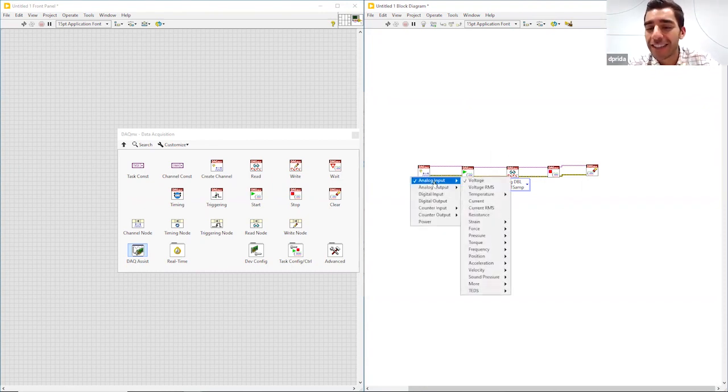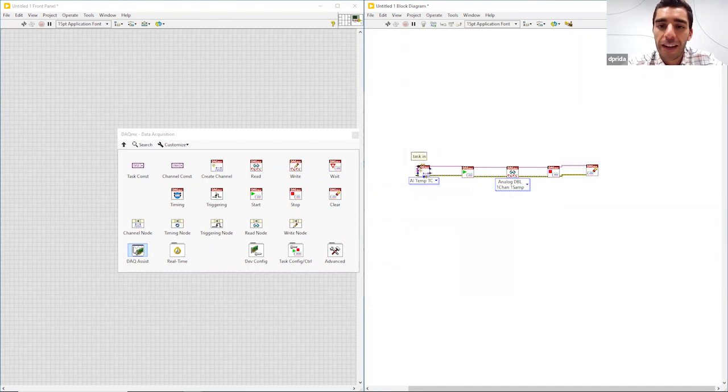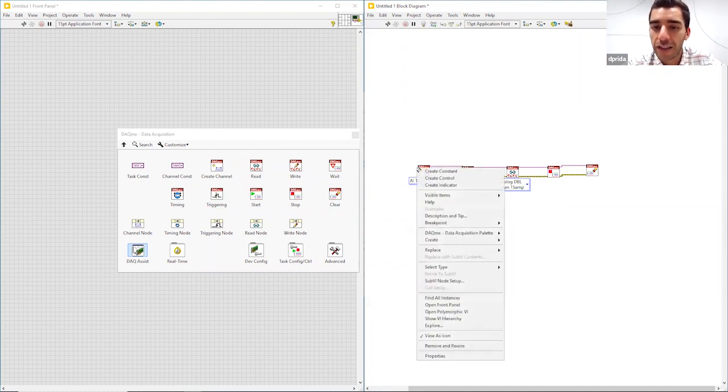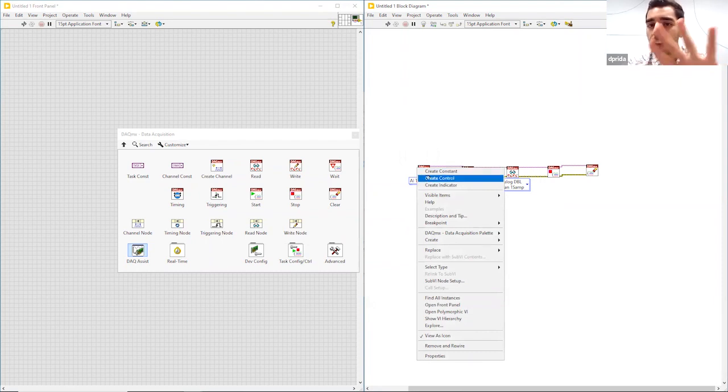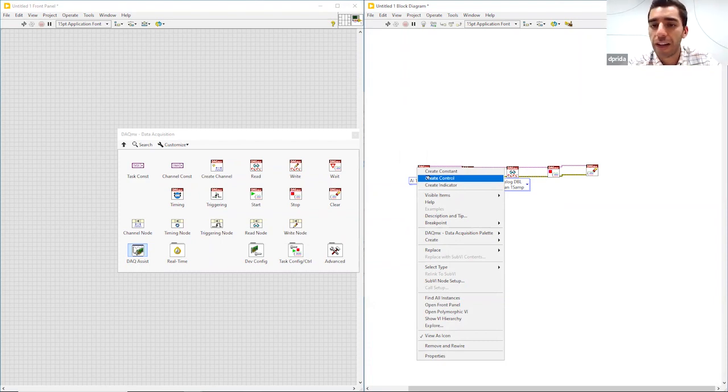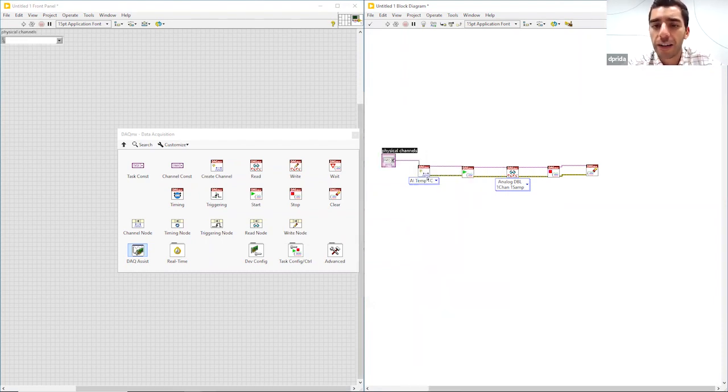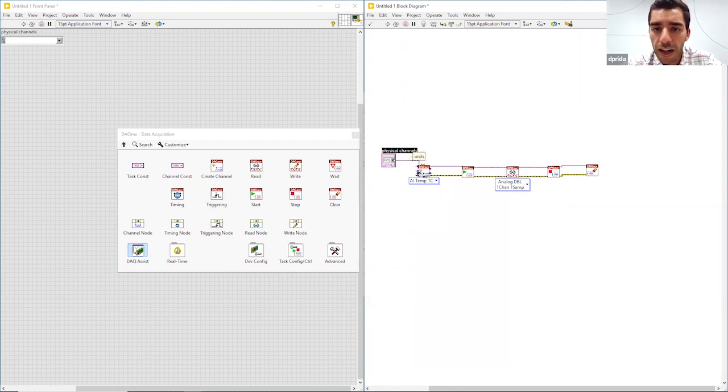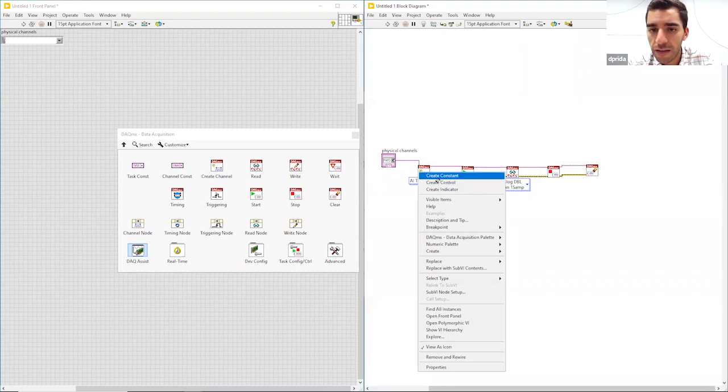So we have it set up. It's defaulted to analog input voltage. We're going to go ahead and change that to a temperature measurement - it's a thermocouple. And then we're going to select the actual devices that we want. You can do it as a constant or a control. The constant will just set it on the block diagram and it'll never change, or you can do it as a control where it'll appear on our front panel and our devices may change. So I'm going to create it as a control.